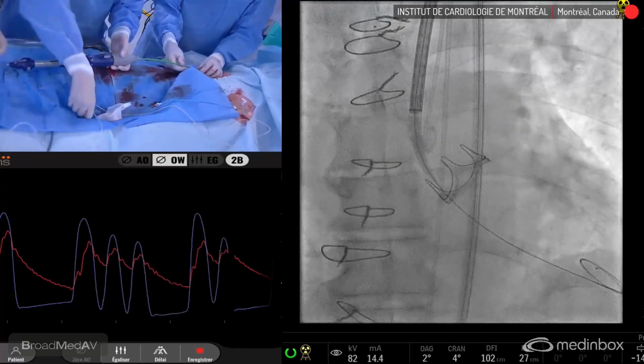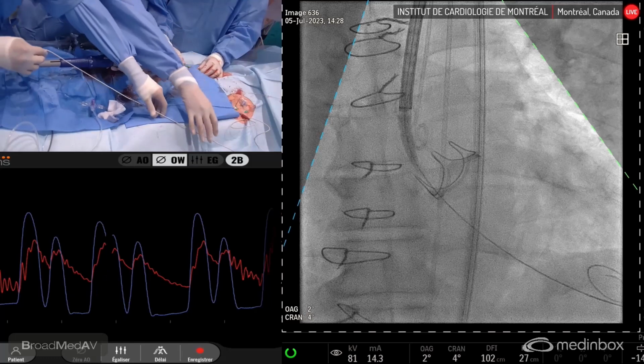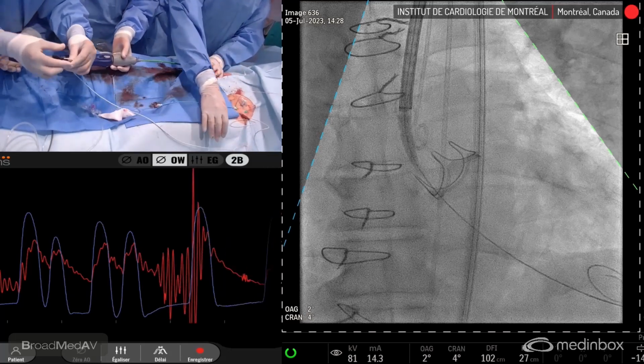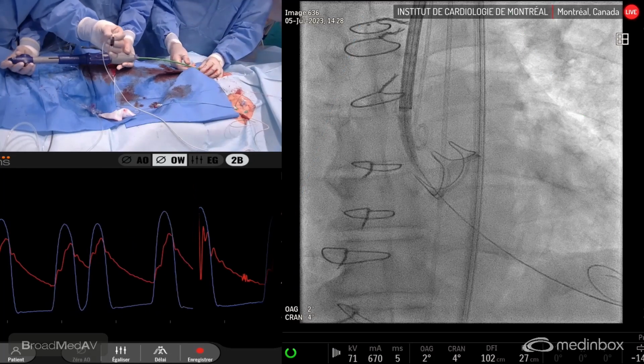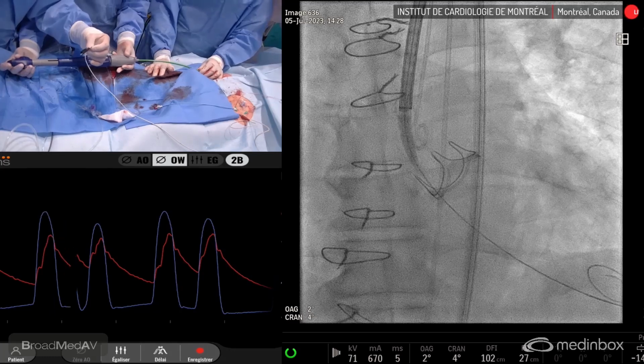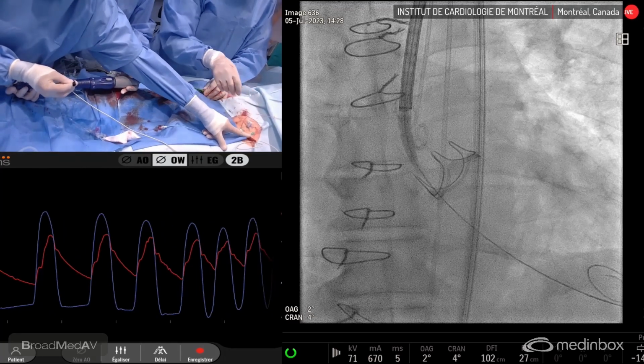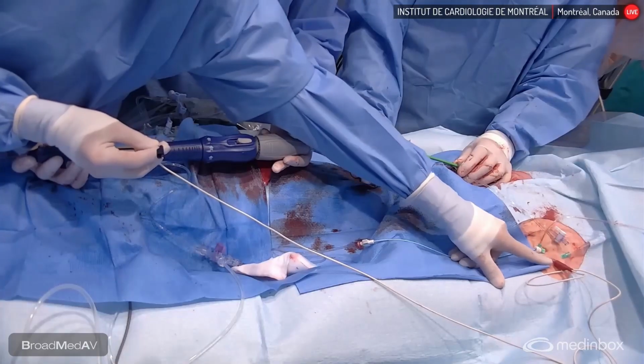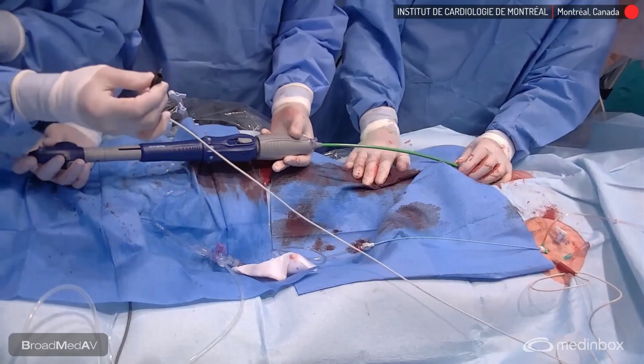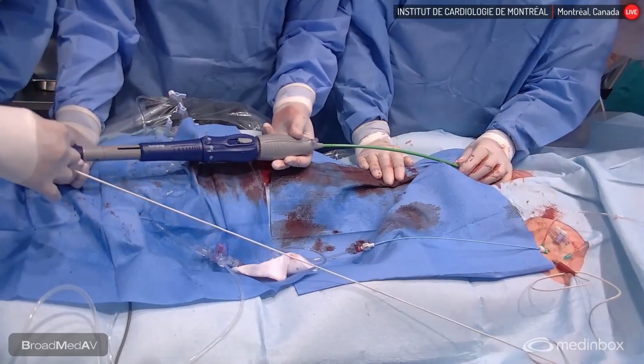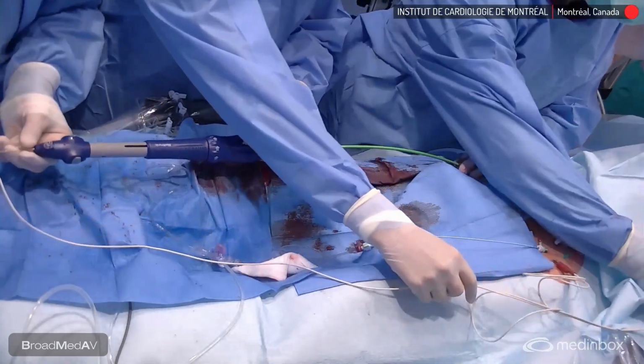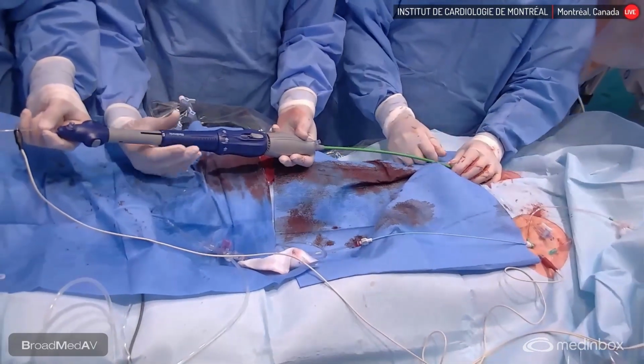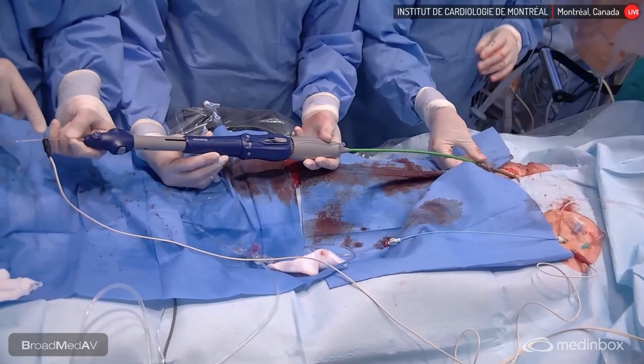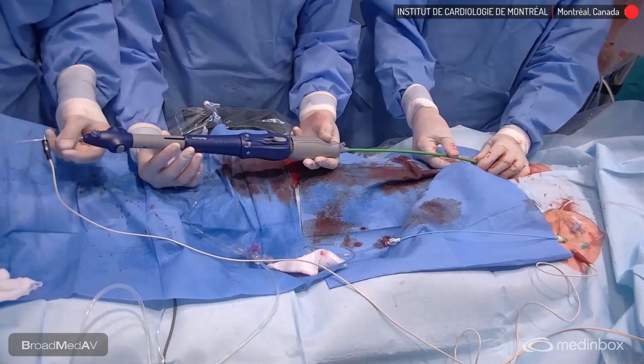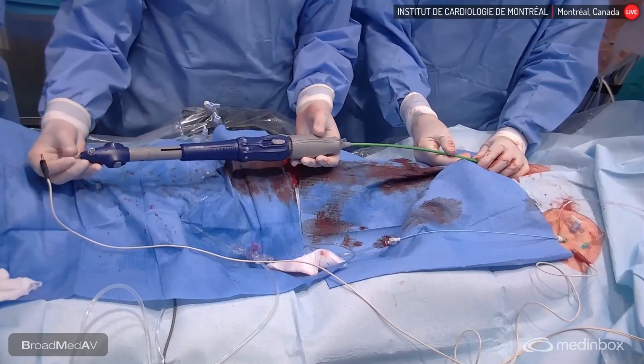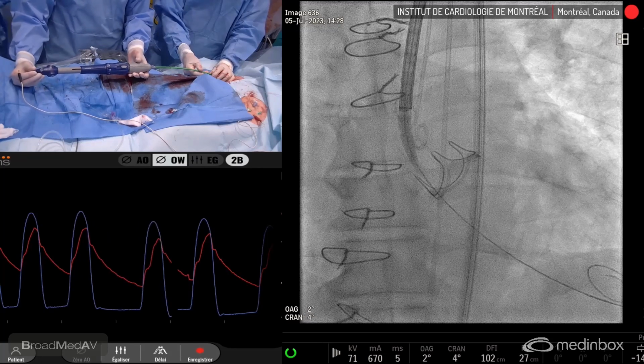Before we cross, I guess we can potentially test the pacing. So I want to show you maybe the setup for LV pacing. As I said in my slide, we have an alligator clamp. It's going to be a unipolar pacing. So we have one clamp here in the groin, in the skin actually. There's a needle, and connected to the needle there's one alligator clamp, and the other one, the black one, the cathode, is going to be connected directly on the wire. There's a specific place that is denuded on the guide wire to place the alligator clamp, but you can actually put that clamp anywhere. It's working, but it's better to put that in that specific area. So we can potentially test the pacing.